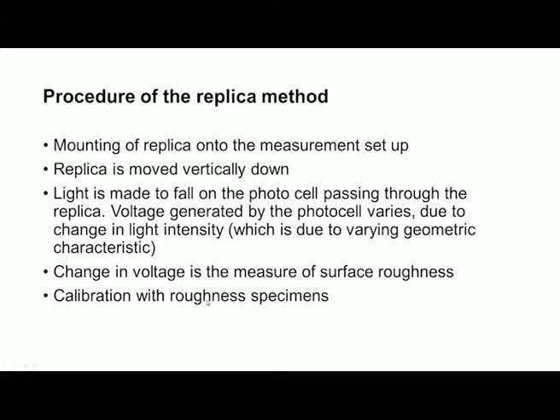Now, what is the procedure of getting the surface finish values in this replica method? Initially we have to prepare the plastic replica as explained, and then it should be mounted onto the measurement setup, and the replica is moved vertically down, and there is a light source. Light is made to fall on the photo cell passing through the replica. The voltage that is generated by the photo cell varies due to the change in the light intensity, which is due to the varying geometric characteristic. Now the change in the voltage is the measure of surface roughness, and proper calibration is to be made so that the replica method can be used, and standard specimens can be used for calibration of the setup.